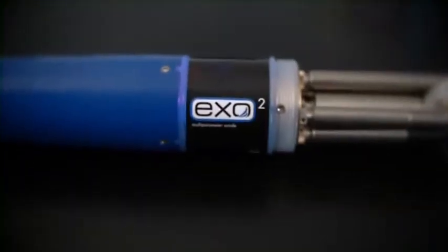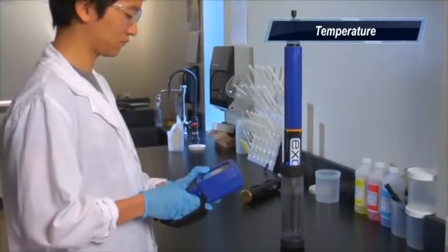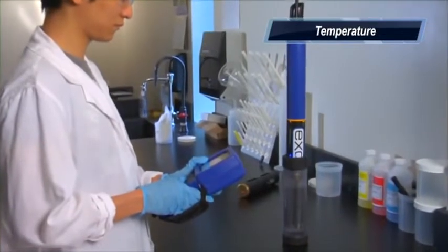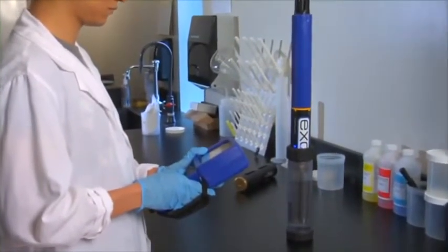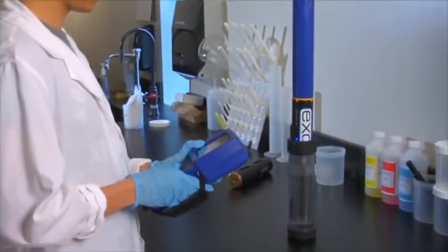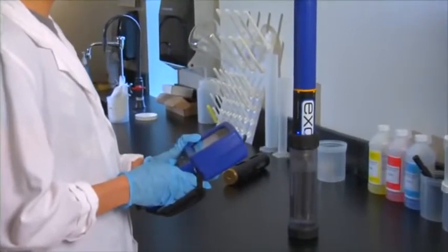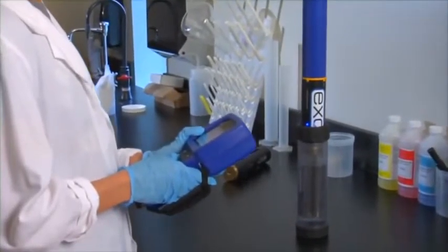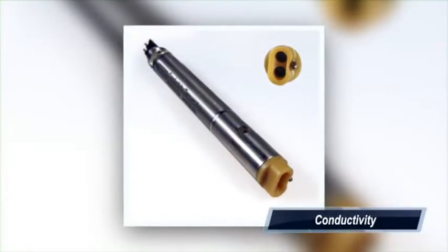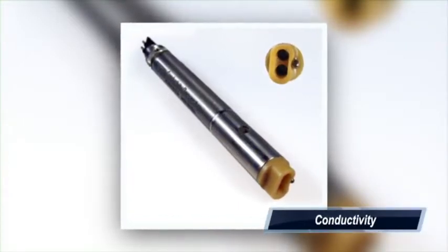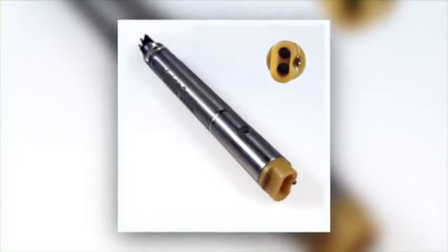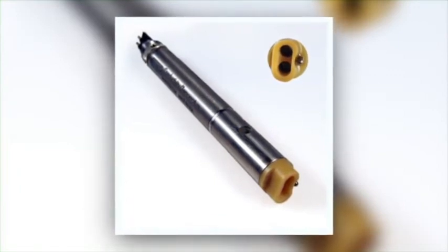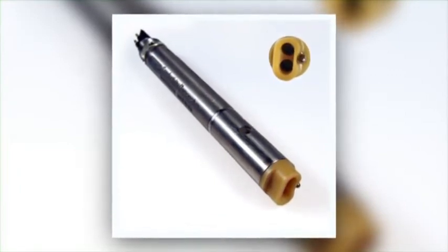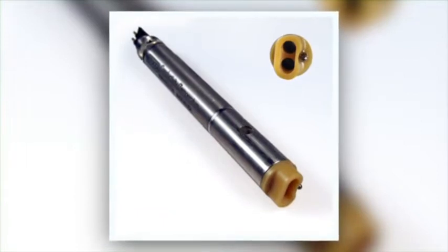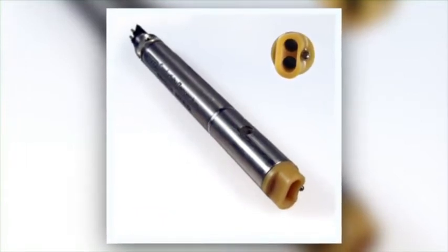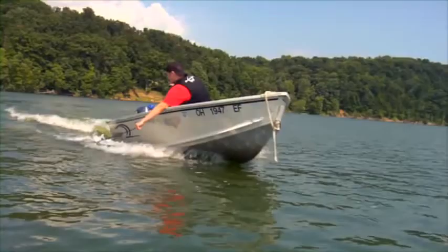The EXO sensors are temperature. The temperature sensor features an accuracy of 0.01 degrees Celsius and a response time which allows the entire sensor suite to operate even faster and provide higher quality data. Conductivity. YSI's conductivity sensor features a double-barrel design housed in impervious titanium casings. The internal flow cell design has been improved to exhaust bubbles which could interfere with sensor readings.